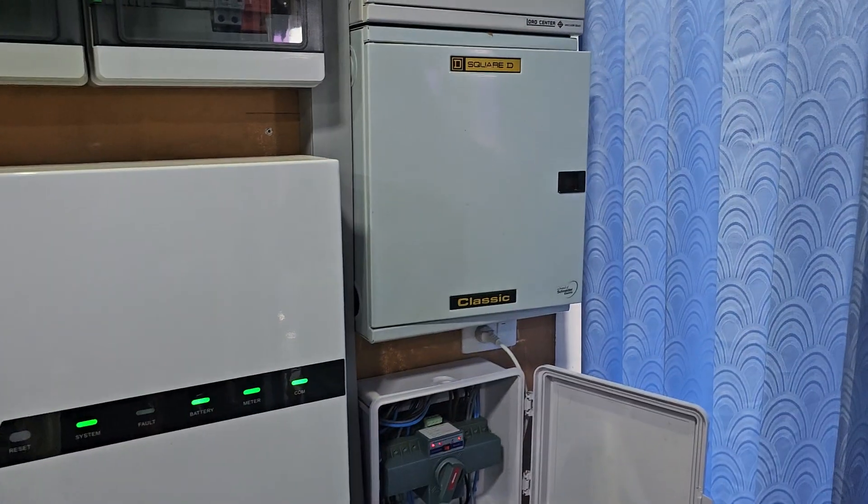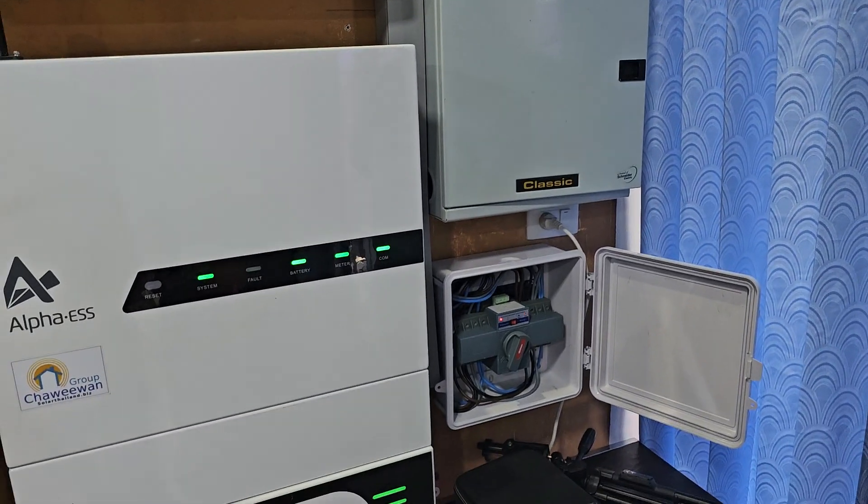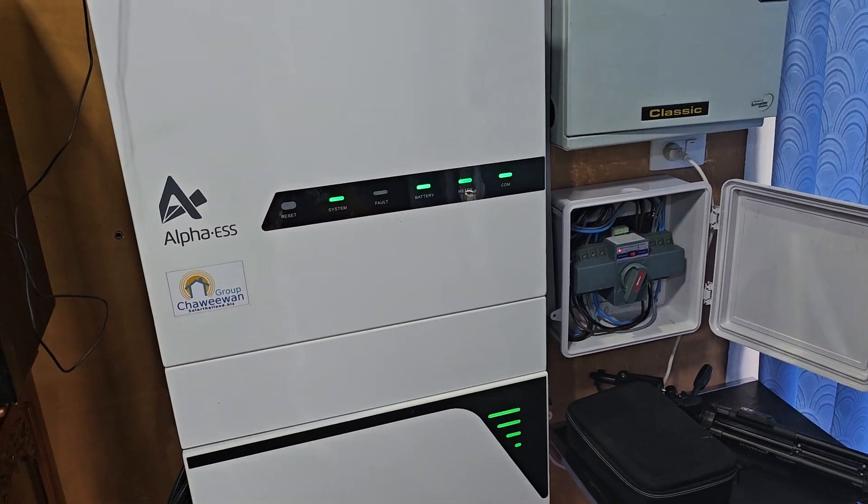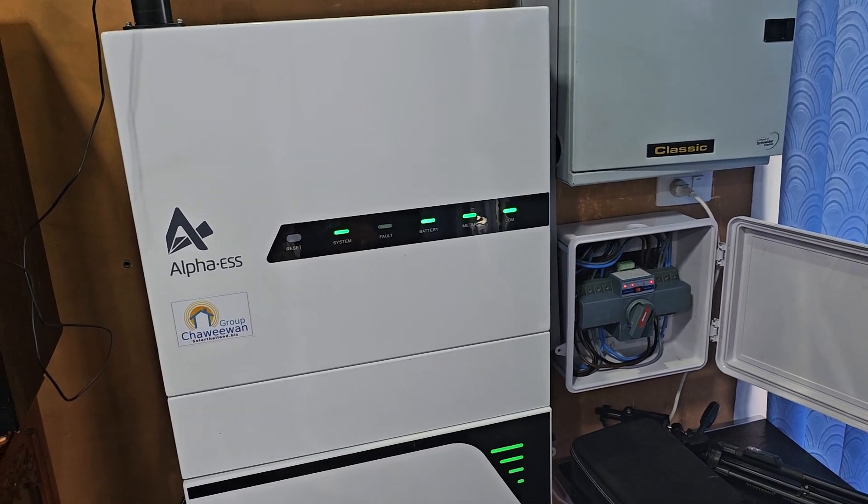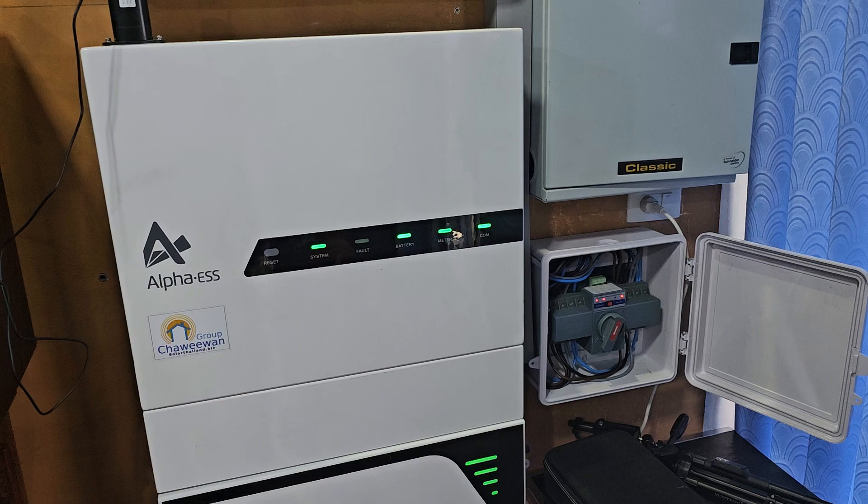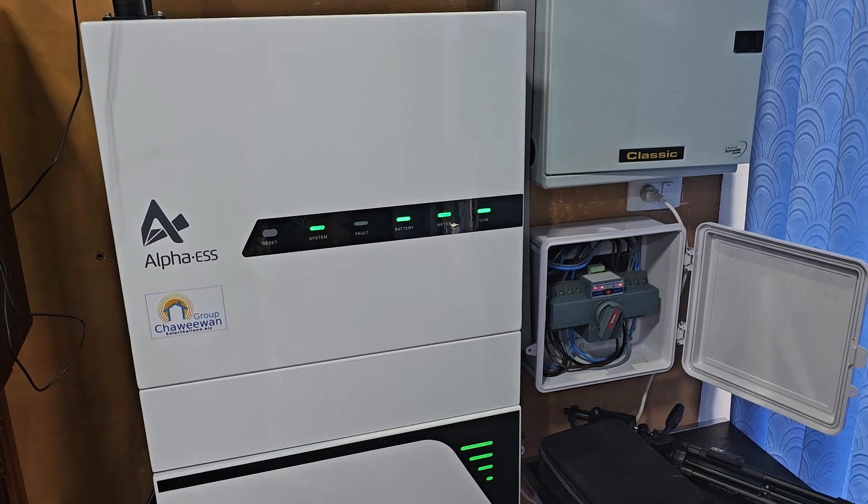Well, because on the UPS there is a limitation on this system of 3.3 kilowatt per phase. So let's say that the worker puts on a machine that takes more than that, the system will overload.